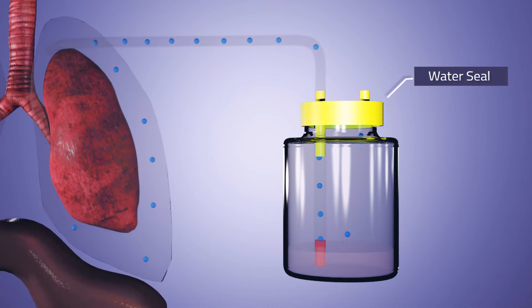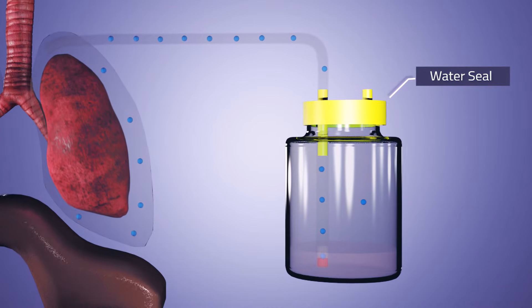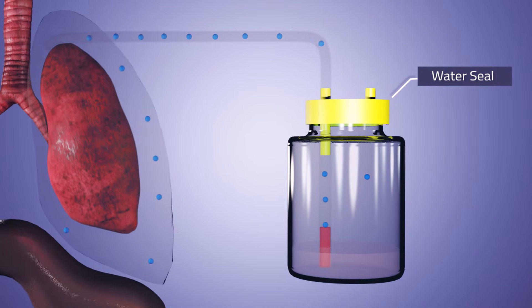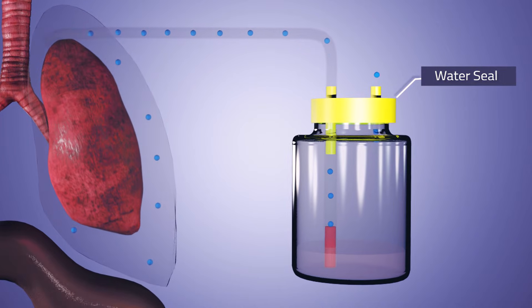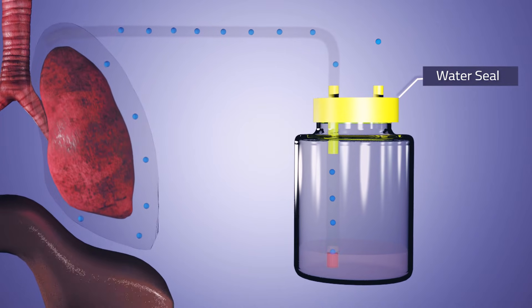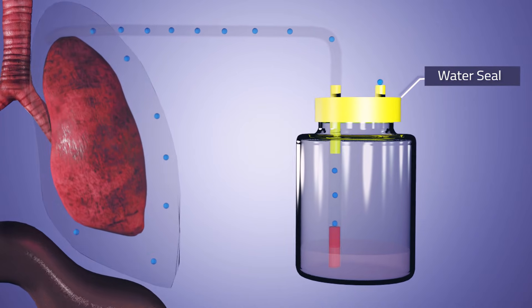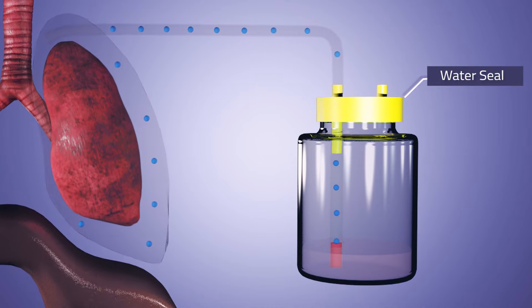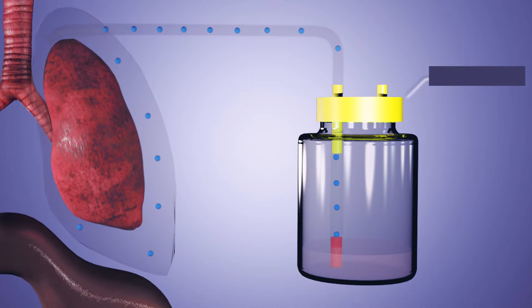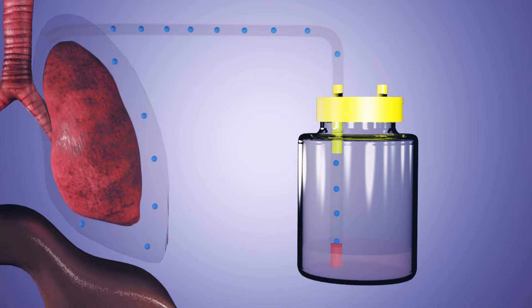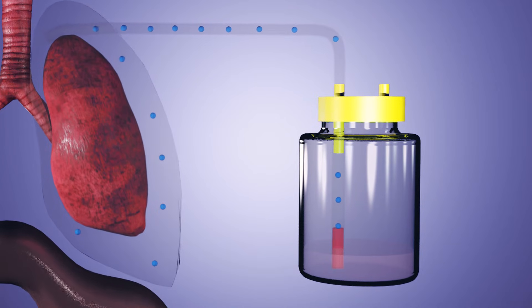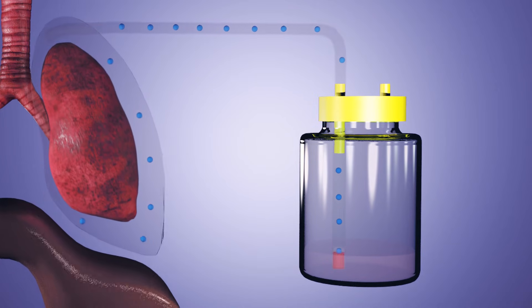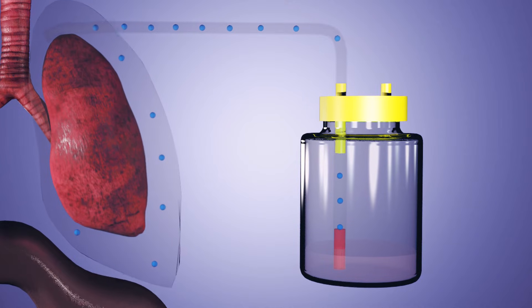With each exhalation, the diaphragm rises and expels the air through the drain. On inhalation, the diaphragm descends and pulls the lung, expanding it. Ideally, the cycle would continue until all the air in the pleural space exits, re-establishing the negative pressure and the total expansion of the lung. At the end of the drainage, the pressure generated by the compression of the air remaining in the pleural space and in the drain is not enough to allow passage through the water seal.